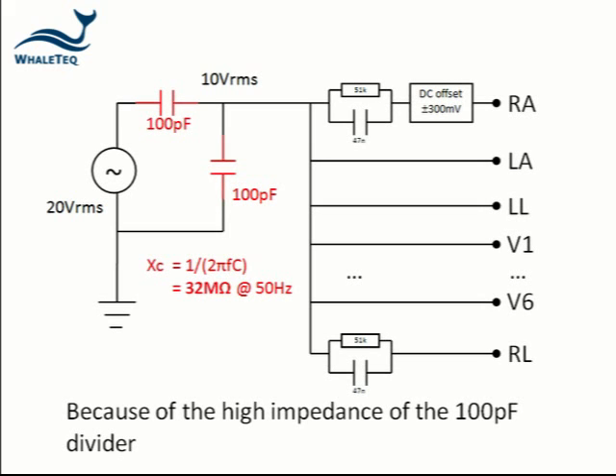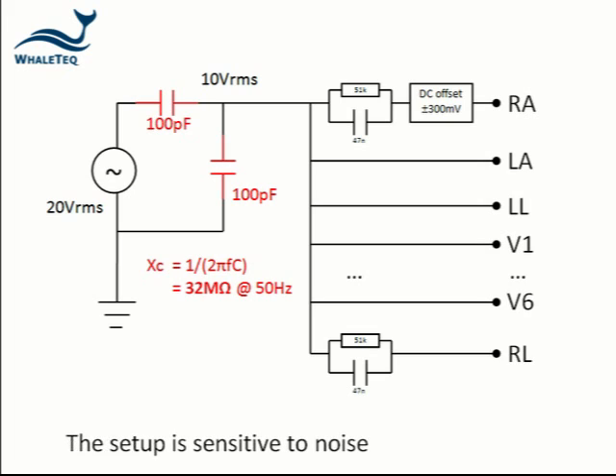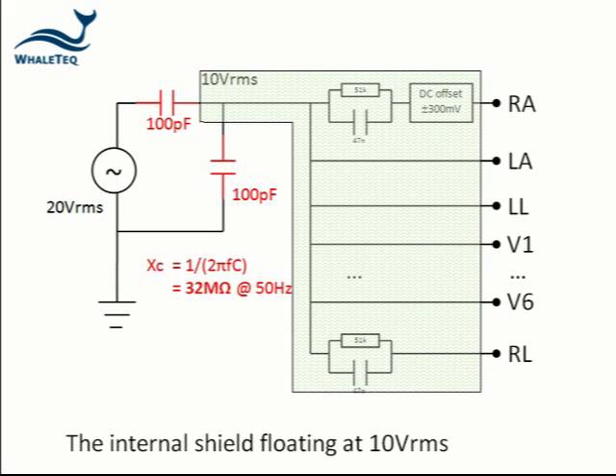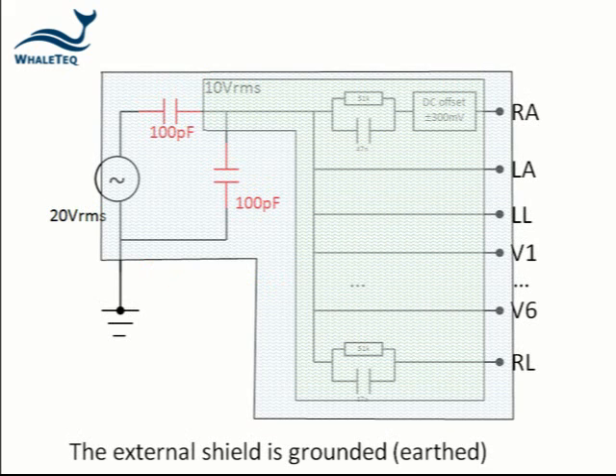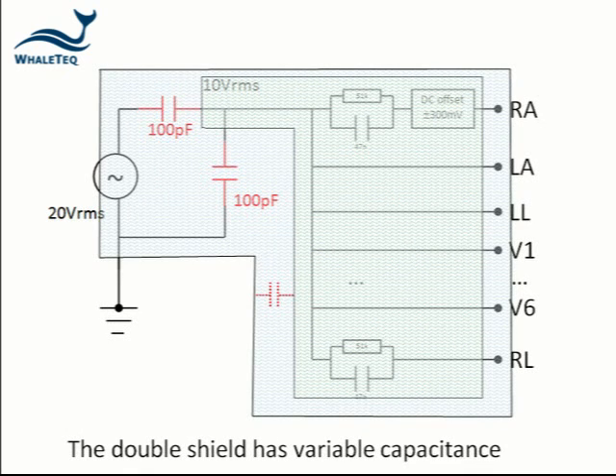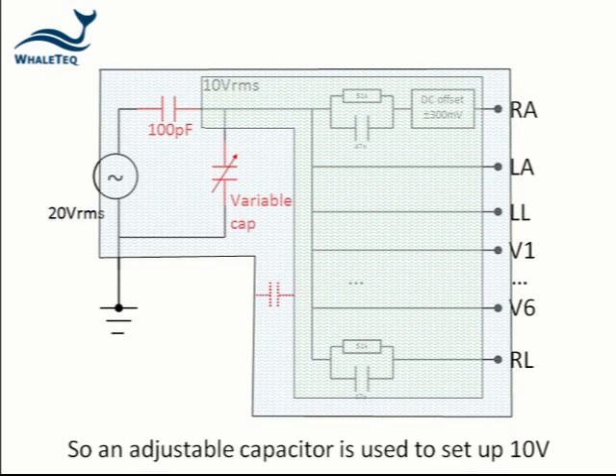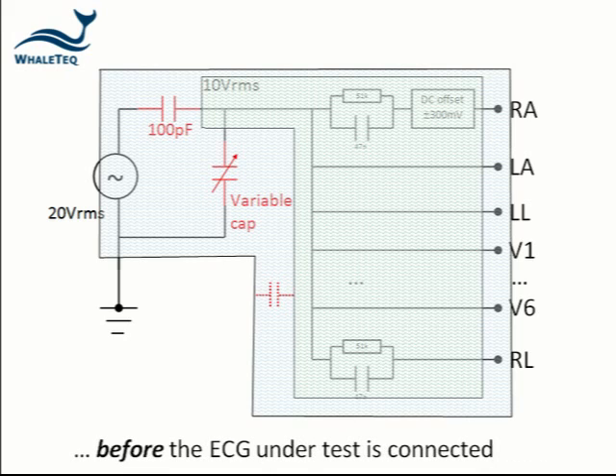Because of the high impedance of the 100 pF divider, the test setup is very sensitive to external noise. For this reason, the standard requires a double shield construction, with the internal shield floating at the common mode voltage of 10 volts, and the external shield grounded. The double shield has a variable capacitance, so an adjustable capacitor is used to set up the 10 volts RMS before the equipment under test is connected.